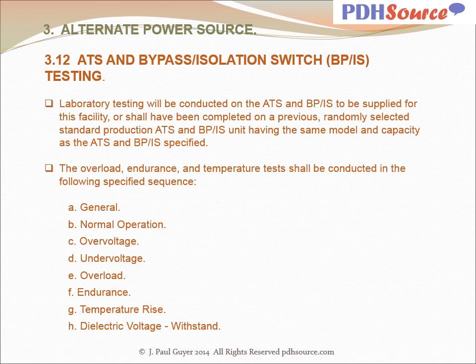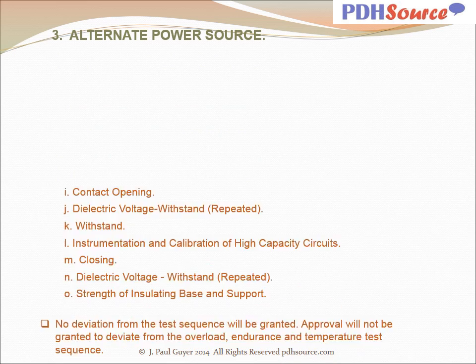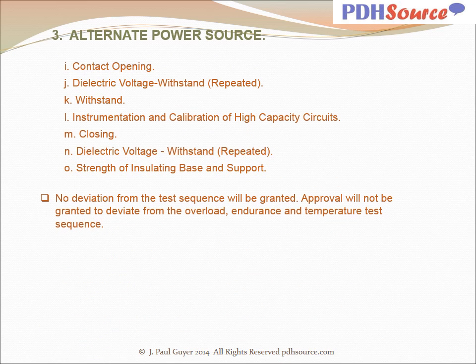The overload, endurance, and temperature tests shall be conducted in the following specified sequence: general, normal operation, overvoltage, undervoltage, overload, endurance, temperature rise, dielectric voltage withstand. Contact opening, dielectric voltage withstand repeated, withstand, instrumentation and calibration of high capacity circuits, closing, dielectric voltage withstand repeated, strength of insulated base and support. No deviation from the test sequence will be granted. Approval will not be granted to deviate from the overload, endurance, and temperature test sequence.